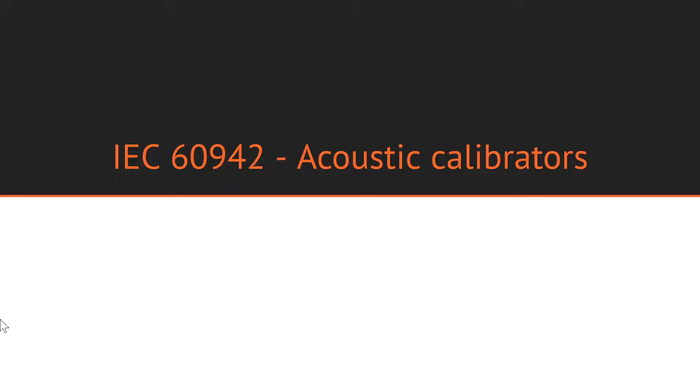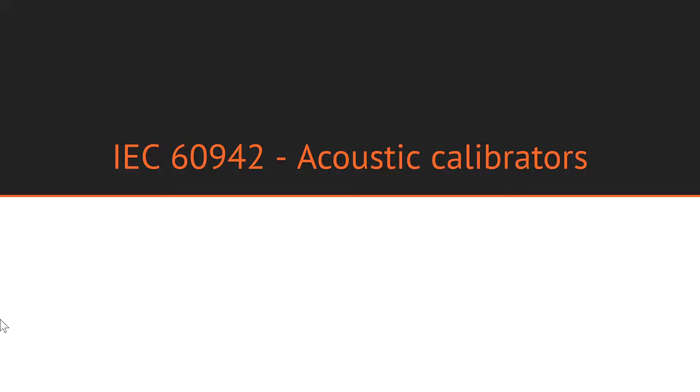In addition to performing a calibration of sound level meter and octave filters, before performing the actual measurement, microphones that are going to be used should be calibrated for level by utilizing an acoustic calibrator. In order for this level calibration to be effective and true, we need to be sure that the output of the calibrator we are using is spot on. For this reason, calibration of the calibrator itself is performed according to IEC 60942.